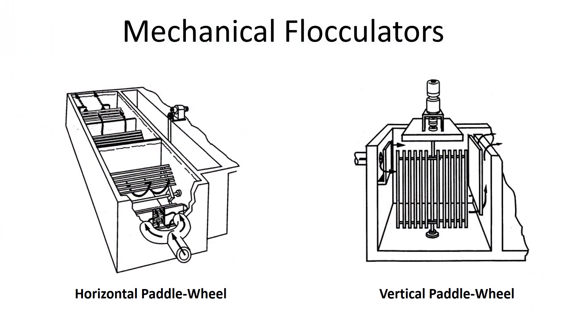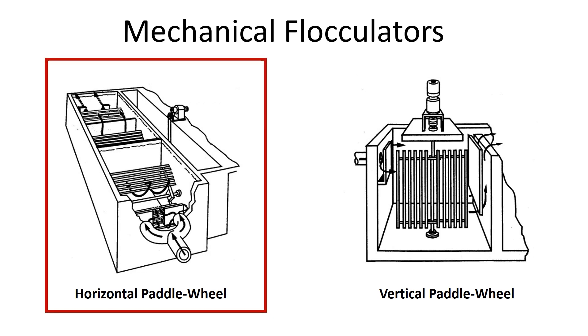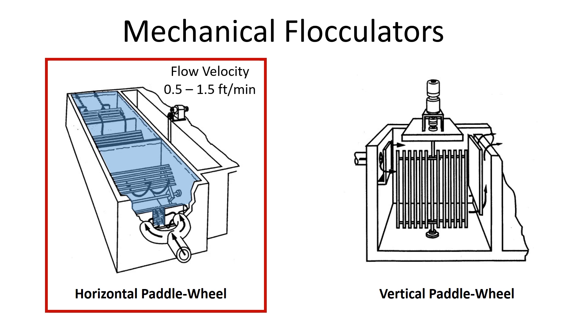Here we have two types of mechanical flocculators. The horizontal paddle wheel allows water to move through from end to end, with the paddle wheels moving in a horizontal fashion to cause gentle mixing. The water flows through the flocculation basins at a flow velocity of 0.5 to 1.5 feet per minute.